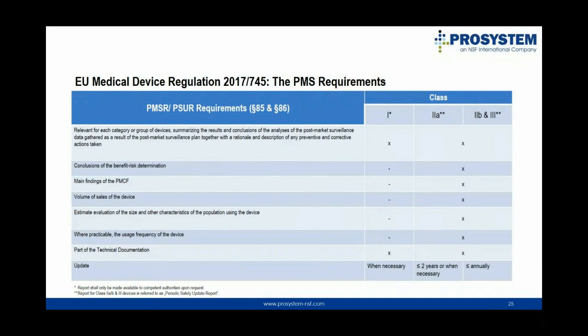Since the PMS activities should be appropriate to the risk class and device type, so do the PMS reports. Class 1 devices demand less effort when compared to the periodic safety update report, which we will talk about in detail in a minute. The PMS report for Class 1 devices merely needs summaries of the results and conclusions of the PMS activities, as well as rationales and descriptions in case any corrective or preventive actions were performed. There is no periodic updating required for the PMS report. In fact, the manufacturer needs to determine situations when the PMS report requires update.